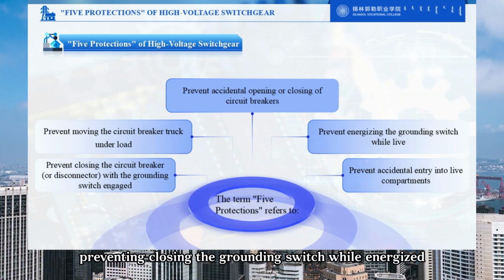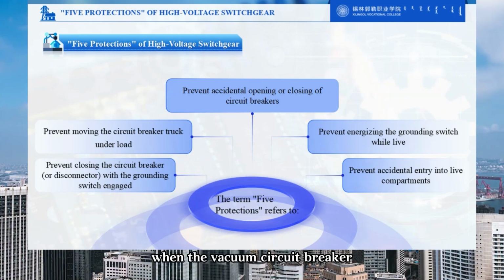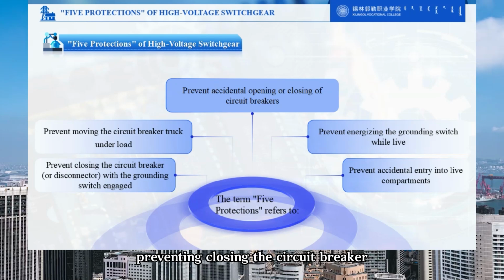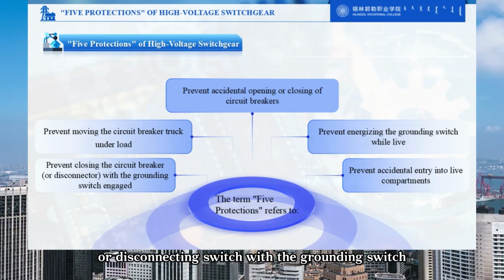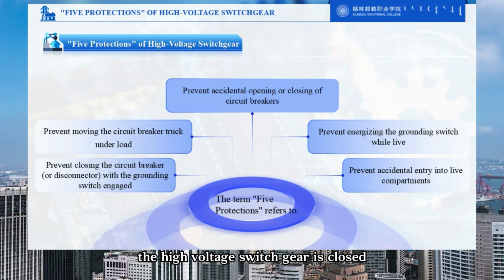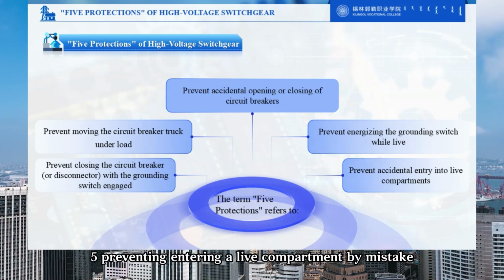Preventing closing the grounding switch while energized. When the vacuum circuit breaker truck inside the high voltage switchgear is in the working position and closed, the grounding switch cannot be closed. Preventing closing the circuit breaker or disconnecting switch with the grounding switch closed. When the grounding switch inside the high voltage switchgear is closed, the circuit breaker truck cannot be closed. 5. Preventing entering a live compartment by mistake.